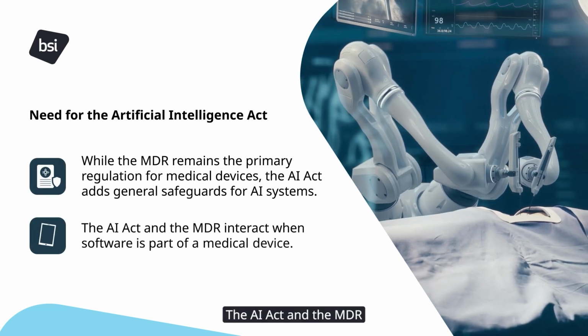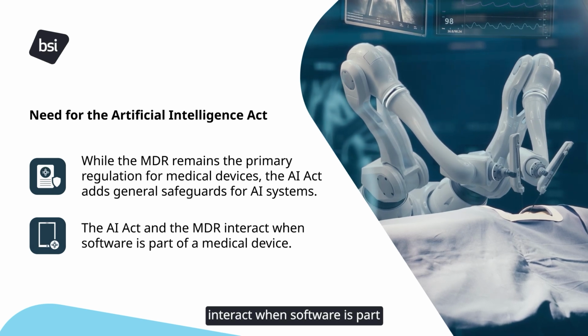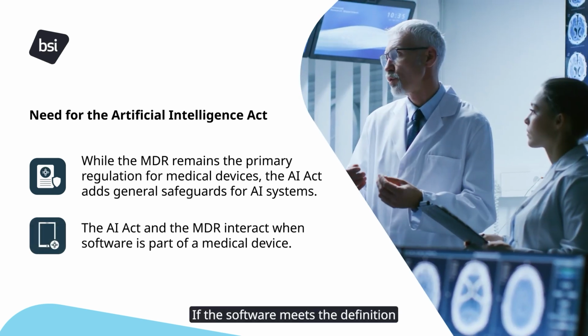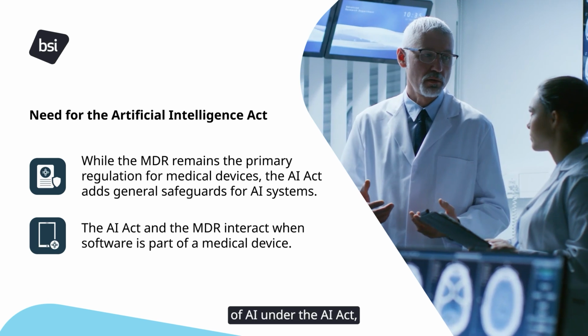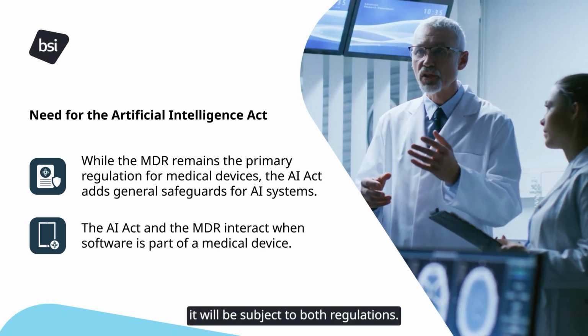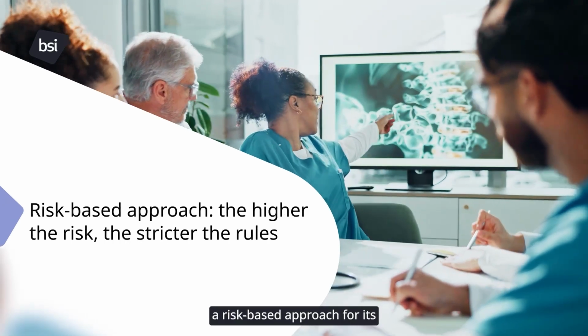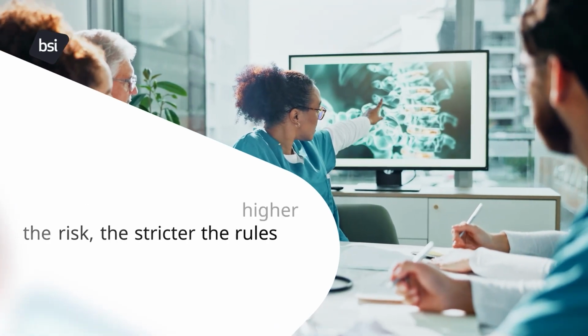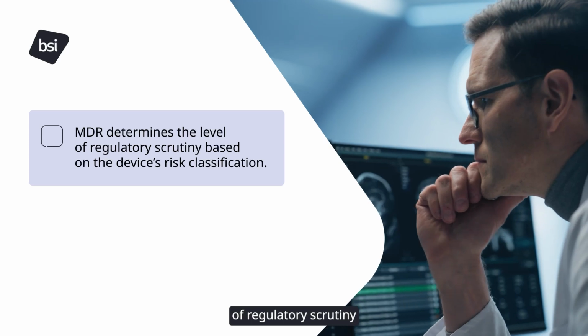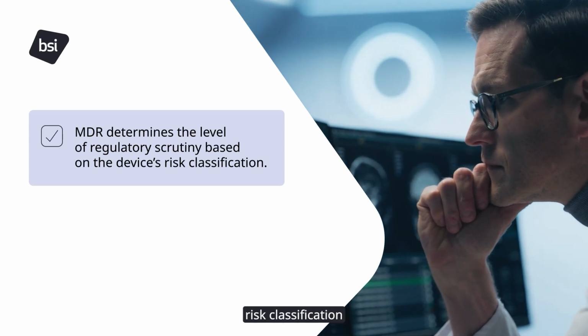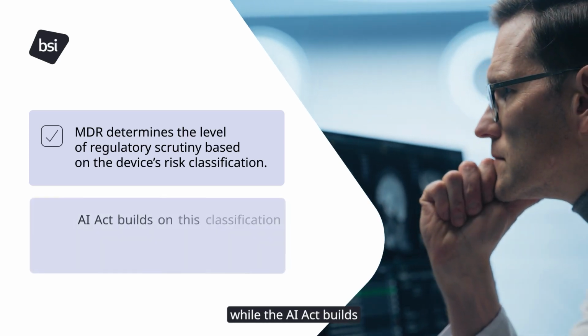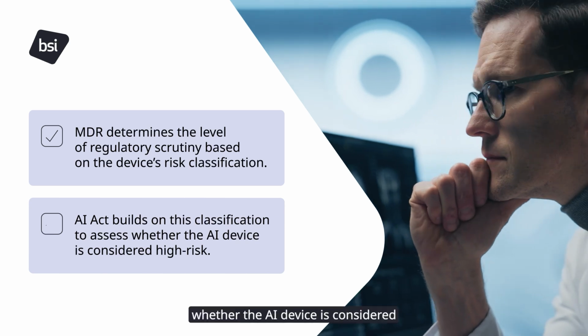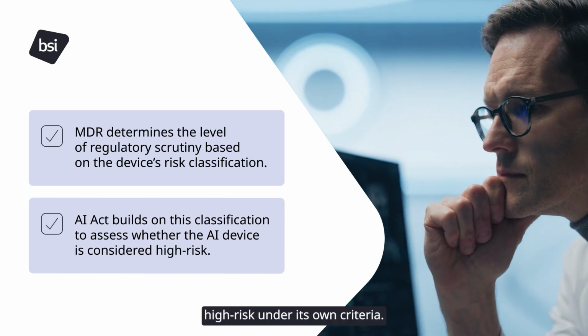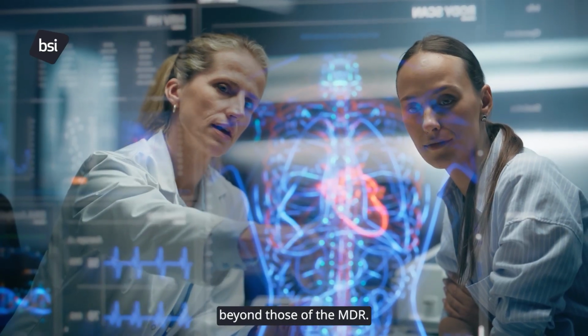The AI Act and the MDR interact when software is part of a medical device. If the software meets the definition of AI under the AI Act, it will be subject to both regulations. Both the MDR and the AI Act follow a risk-based approach for their classification rules. The MDR determines the level of regulatory scrutiny based on the device's risk classification, while the AI Act builds on this classification to assess whether the AI device is considered high risk under its own criteria. This adds extra requirements beyond those of the MDR.